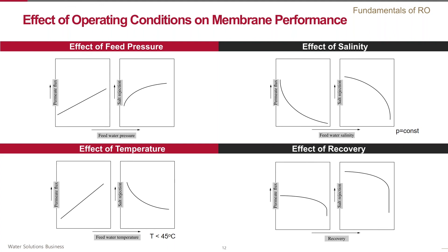The flux increases with temperature while the rejection goes down — both phenomena are related to diffusion through the membrane. Finally, regarding the recovery effect: as recovery increases, the water flux decreases because of the increase in osmotic pressure, until recovery is so high that the osmotic pressure of the feed water equals the applied pressure, at which point the driving force for water through the membrane becomes zero and flow stops. The drop in water flux affects the apparent salt rejection in a similar way.